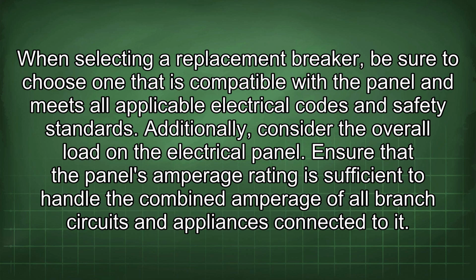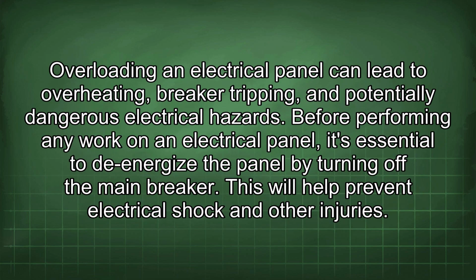Ensure that the panel's amperage rating is sufficient to handle the combined amperage of all branch circuits and appliances connected to it. Overloading an electrical panel can lead to overheating, breaker tripping, and potentially dangerous electrical hazards. Before performing any work on an electrical panel, it's essential to de-energize the panel by turning off the main breaker. This will help prevent electrical shock and other injuries.